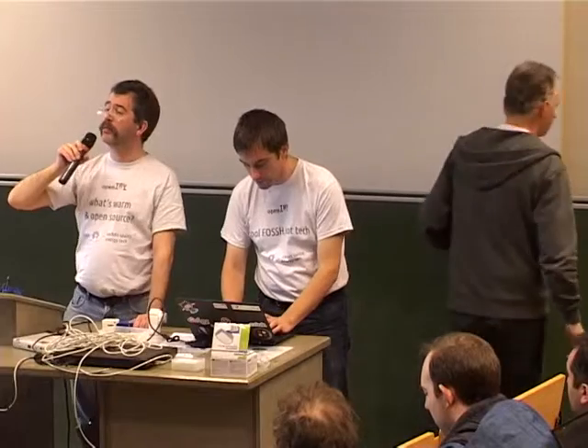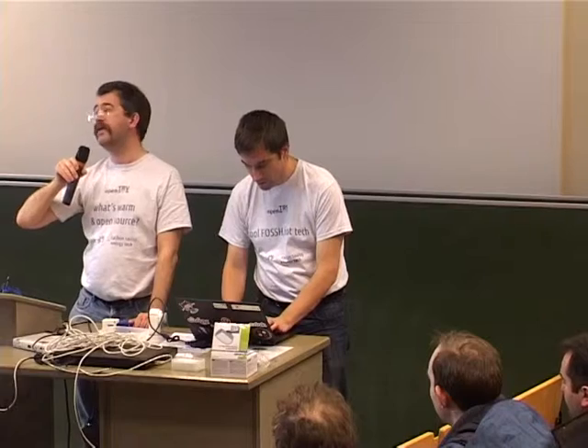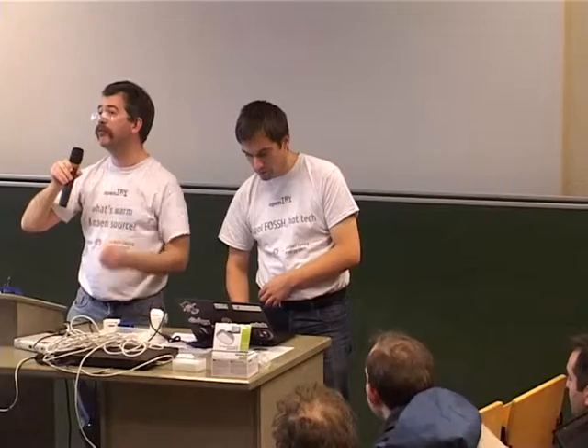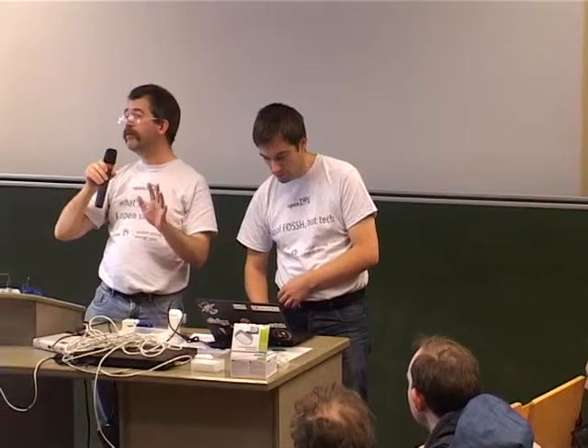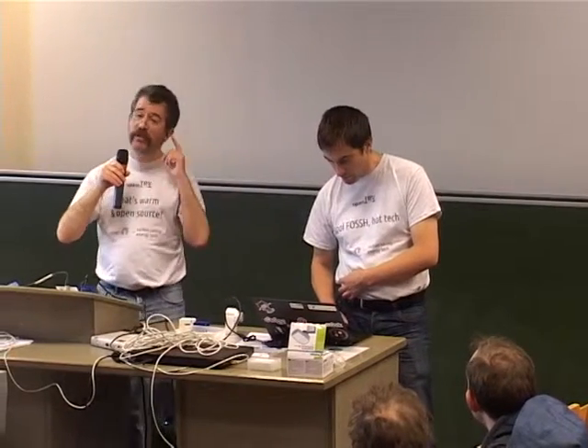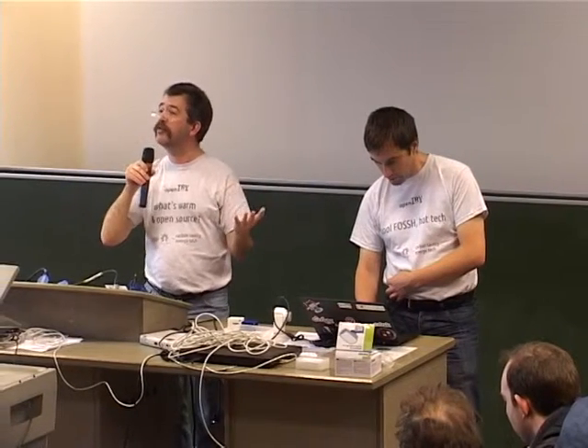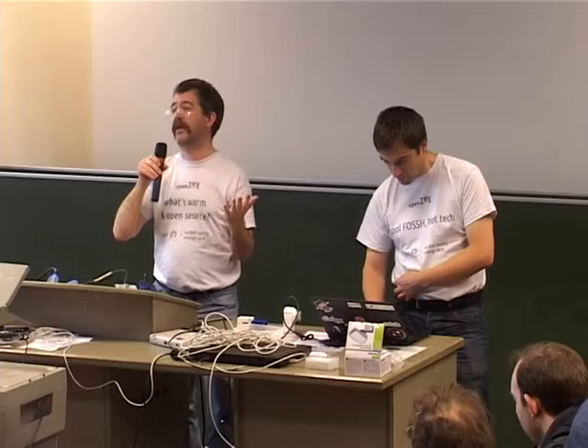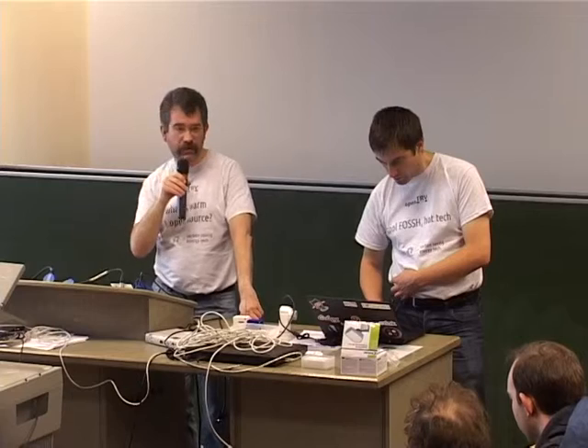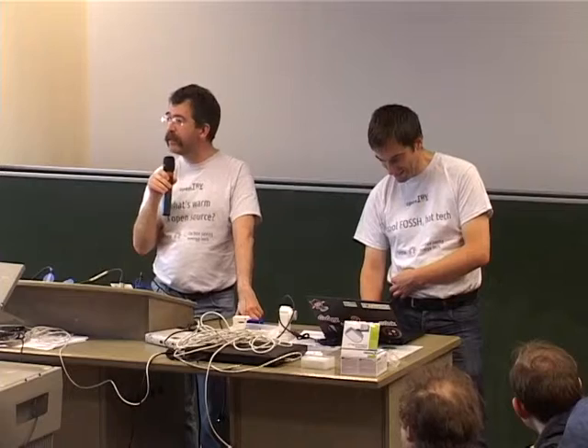I think you've discovered what we call an oversight. I've forgotten to put such a thing in. It's dead easy. Every radiator is controlled locally, as you would if you had an electronic radiator valve, just to keep the room level. And the only special thing we've done here, what us in engineering would obviously call a hack, a filthy hack in fact, is that the thing at the boiler just eavesdrops on the conversation. If any radiator valve is open, it switches the boiler on. Now, we'll have a more sophisticated topology, but the whole thing is currently done by eavesdropping. I'm expecting the NSA to turn up at any moment and ask for advice. But that's all it is. It's a filthy hack, and it works.